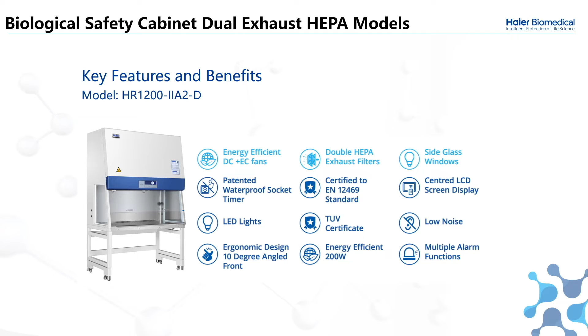Now, there are a few benefits which we see in the UK from a dual exhaust HEPA. The extra HEPA offers you extra protection in the event of a filter failure. It makes people more comfortable working with higher containment, for example, hazard group 2, in an environment where you don't have any ducting. By not having any ducting, you also reduce the cost and the ongoing cost, as running a ducted extract system can be expensive and it can add a lot to installation. Without having ducting, it's much easier to install a new cabinet and it reduces the cost of the installation. There are a few more things on this page which go through the pros and cons, but something to take away is that when having a dual HEPA, it reduces the requirement for a ducting system.